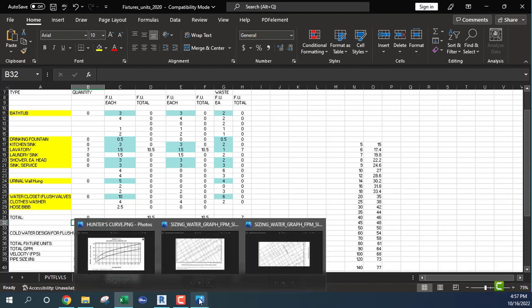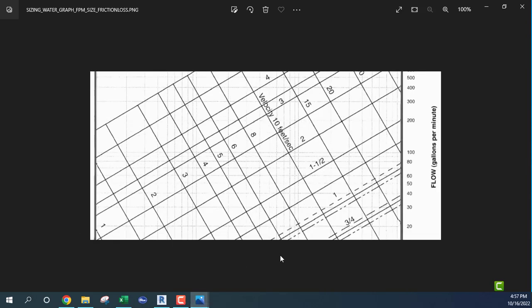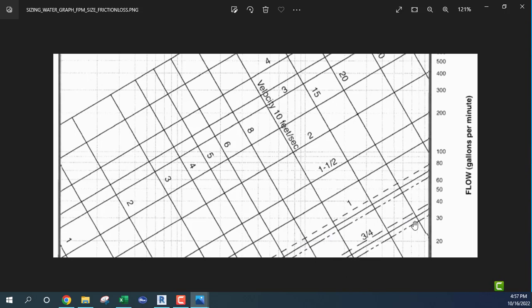Now what we need to do: I have 28 GPM — let's call it 30. I want to keep the velocity between 6 and 7 feet per second. Looking at the chart, I would increase that to one and a half inches to supply four lavatories.